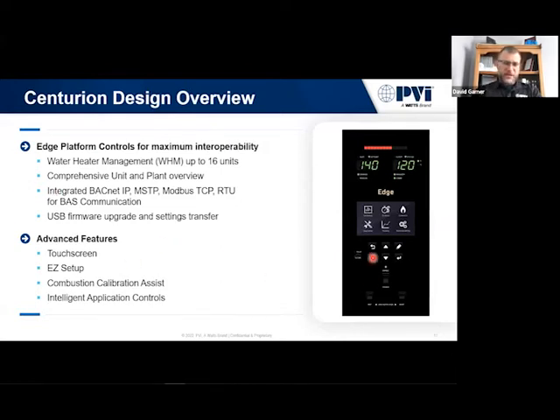There's a USB connection on the side. This is what we use for doing firmware updates, software updates. But a really nice feature is, here at altitude, it's a lot more work involved to do combustion calibration. Say we have a site that's got 4 units there. We get the first unit set up, we get the combustion settings in there, from the get-go, since these are coming up from sea level. But once we have that first unit calibrated, we can actually take that information, those combustion settings, and clone it over to the rest of the water heater plant and be able to do the fine tuning on the individual units.